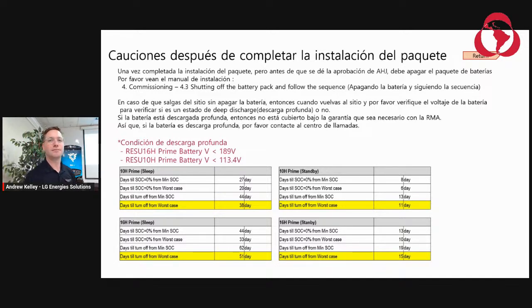What happens if you drain the battery all the way to 0%? Good question — the battery has a fail-safe, a reserve. So unless you go in and override certain things — figure out how to override it, which isn't really likely — you're not going to be able to drain it all the way to zero. Unless you tell the inverter to do something to drain it fully on purpose, that could be an issue, but generally it's really hard to drain it all the way down. There's always a little left, no matter how well you set it. So you don't have to worry about draining it while commissioning, or during a few days of bad weather. If it shows zero, there's still about 5% left in the battery, enough that it'll turn back on once power comes back or the sun comes up and you get solar power again.